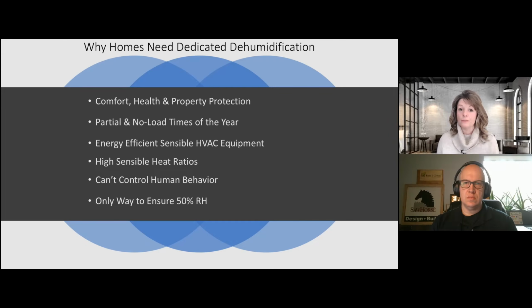Now, our HVAC systems, if you have a home or you're a contractor and you run your Manual Js, you're typically designing that AC system for peak load conditions. The peak load in Atlanta is 92 degrees, so that's what we're going to design our AC system to, and then 75 degrees inside and 50% relative humidity. Typically, the Manual J peak load conditions happen in most locations 1% of the year. So we design and size our HVAC systems to run at that 1% of the year, and then we have to figure out how we're going to handle comfort, temperature and moisture the rest of the year. So it really is the only way to ensure you've got 50%, which is typically what that Manual J design condition is.